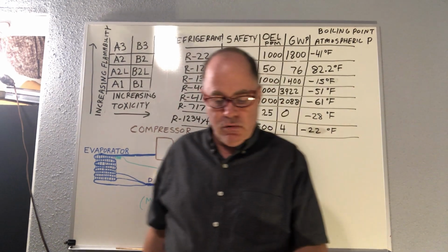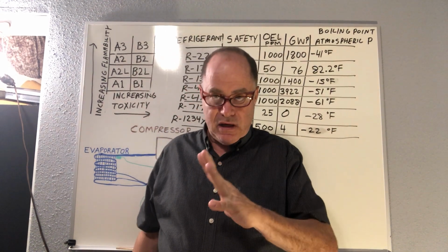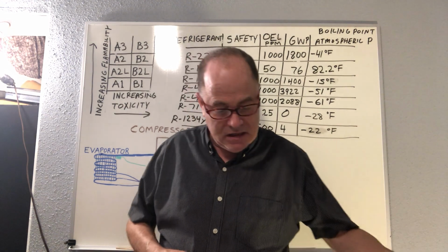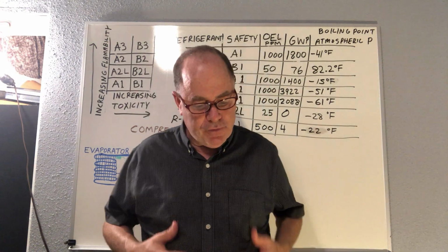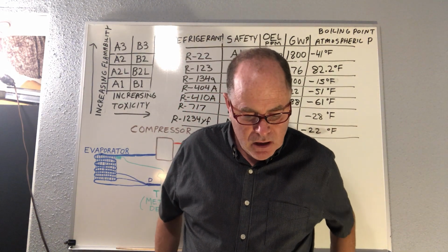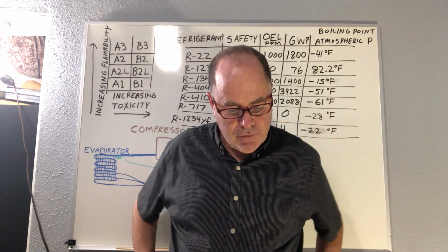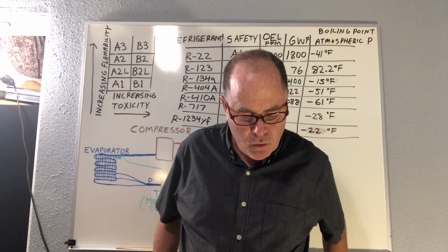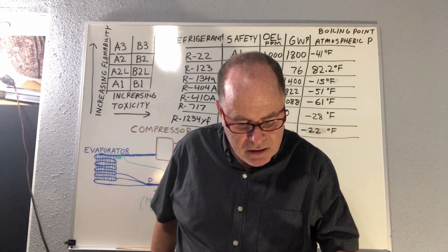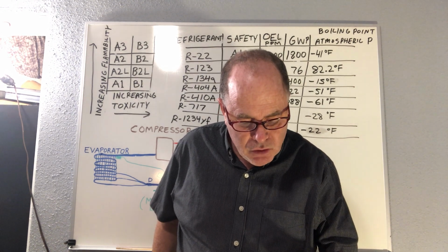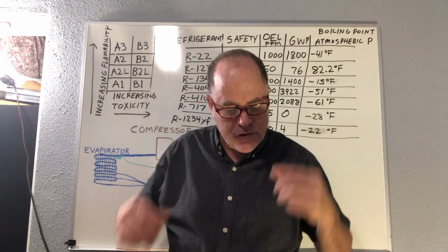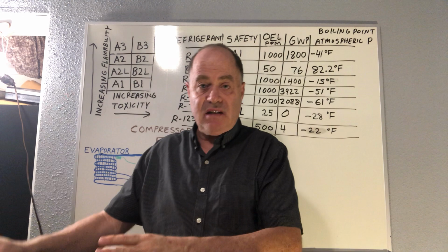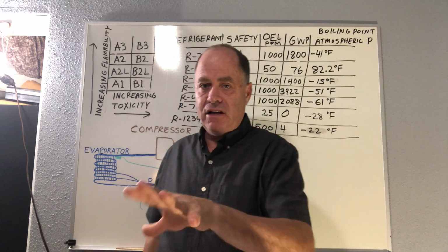If you have a chiller room, it's got to be isolated so that refrigerant can't leak out of it into an occupied space. We're going to talk about recovered refrigerants here. It says here, recovered refrigerants shall not be reused except in the system from which they were removed or as provided. You can use recovered refrigerants also for the same customer. They generally want you to take it out and put it back in the same system. If it's corrupted, they don't want you to do that.